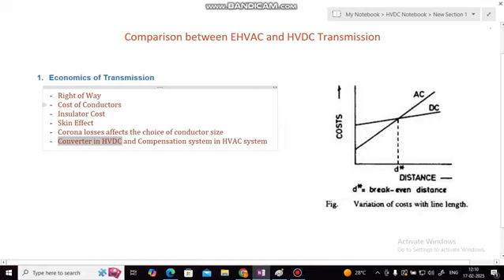So if operating cost is low and distance is increasing, then losses will matter. So after a break even distance, the HVDC will be beneficial, and the cost of HVAC will increase because the operating cost is high for long distance. Because in HVAC system, after 60 to 70 kilometers, there is need of reactive power compensation. So it will increase the initial cost also, and after a long distance there will be operating losses also, like corona losses, skin effect losses.